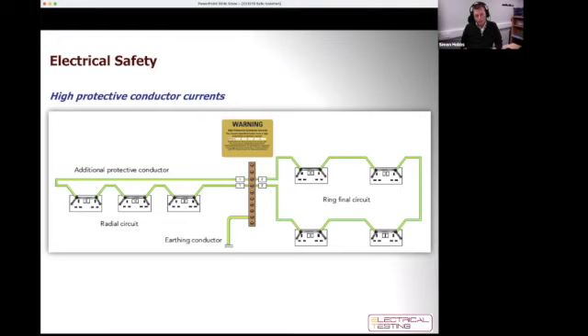So again, if we don't carry out correct and complete safe isolation, it may be that there could still be dangerous currents in play. And the other thing is that with these circulating currents, if we don't have large enough bonding conductors or additional bonding conductors, it might be that I'm working on the circuit and disconnecting an earth bond from a column, for example. I may have 10, 20, 30 milliamps flowing through that bonding conductor due to electronic devices on the network. It may be EV charging devices, it might be LED lanterns and so on. And the electronics within these devices can drive this earth fault current. So we need to be very, very mindful of disconnecting bonding conductors without carrying out correct isolation as well.